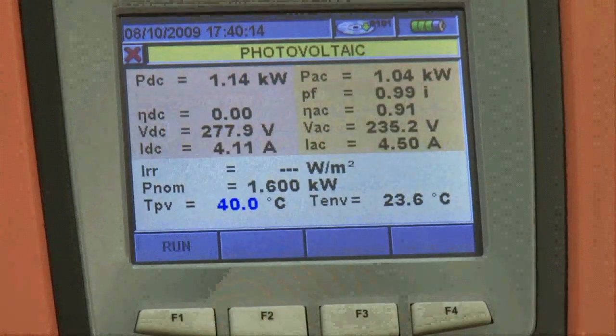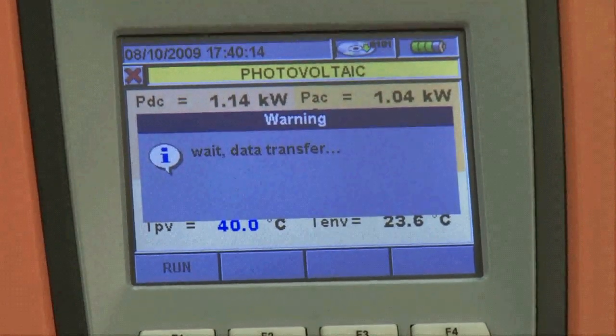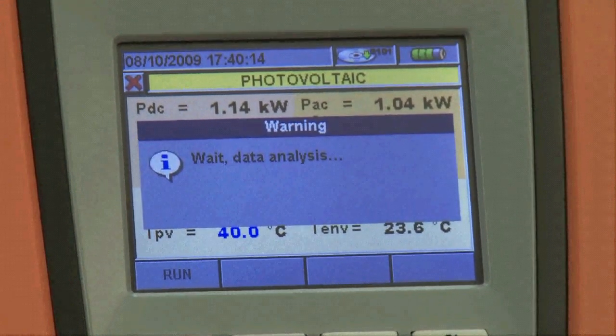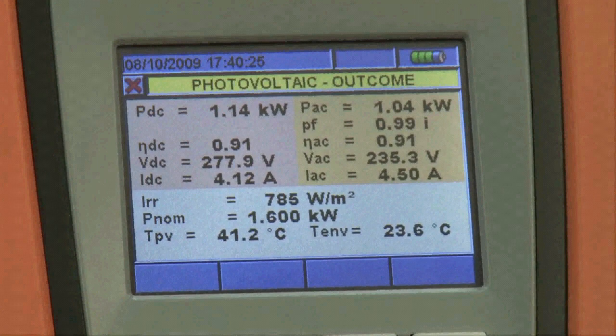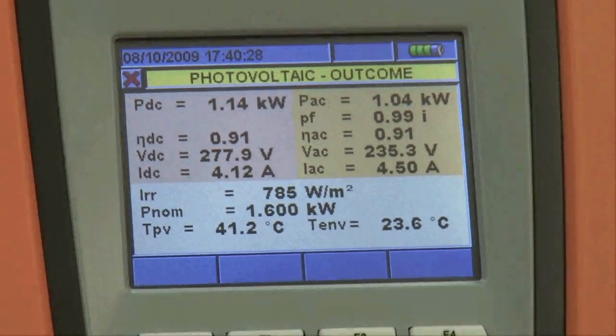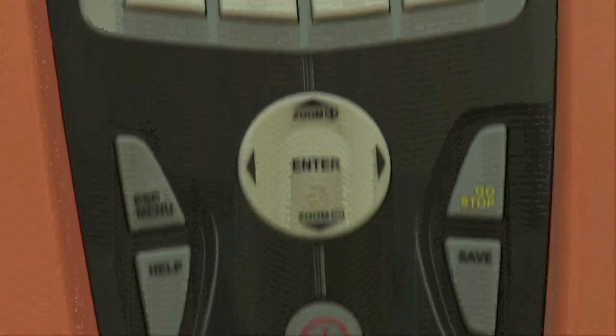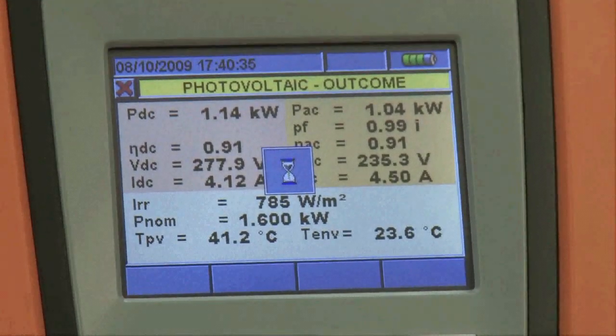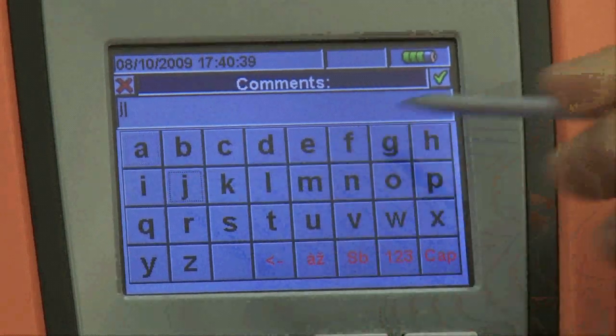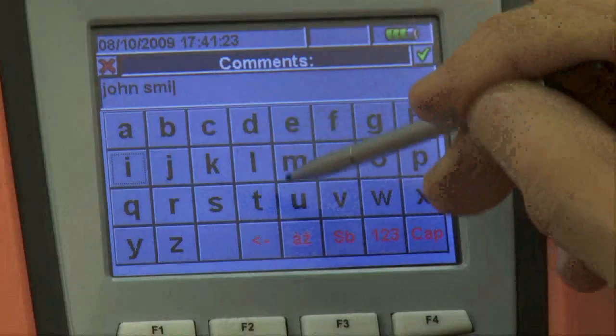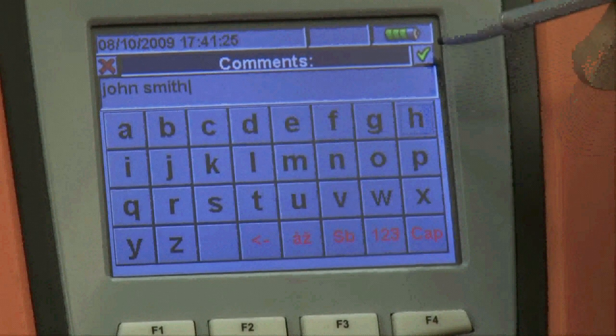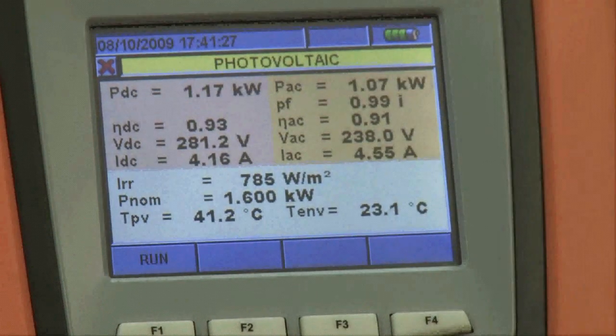The instrument automatically shows the data relevant to the system, displaying the values of the electric and environmental quantities corresponding to the maximum efficiency point detected. All measured data can be saved by pressing the Save key. Thanks to the keyboard on the touchscreen display, it's possible to add a comment to the saved measurement. System testing has been completed successfully, rapidly and with ease.